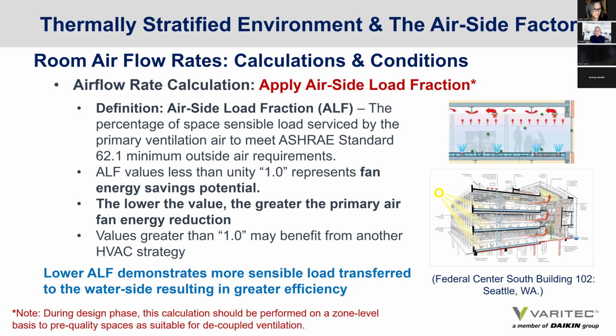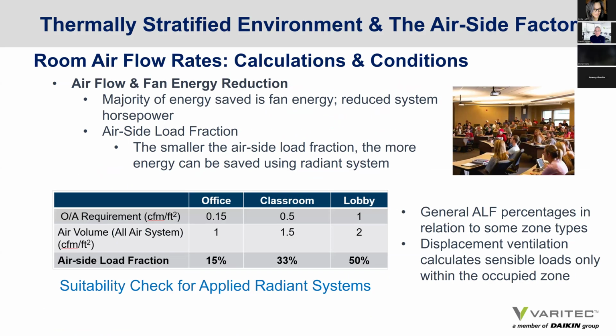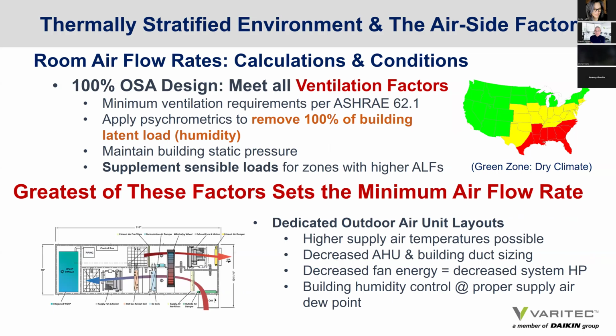So any airside load fraction rate that is calculated to be below 1 represents a fan energy savings, because the sensible load is being effectively driven to the chill water loop, which requires less pumping horsepower than the fan energy horsepower that would otherwise be required. There are some ideas from calculations, roughly, on airside load fraction rates: offices at 15%, so they're ideal; classrooms at an impressive 33%, they can make all the sense in the world; and even lobbies, depending on their architectural design. So when designing radiant systems, it is important that you keep some design factors in mind.